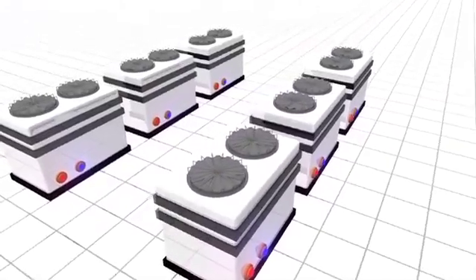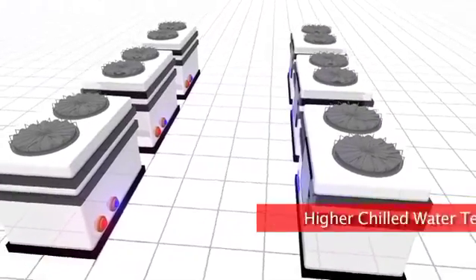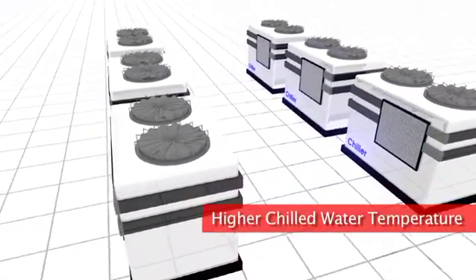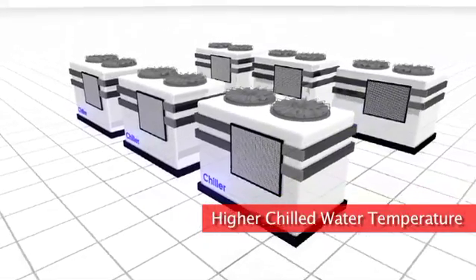With the hot aisle containment we were able to raise our chilled water temperature. This for us meant that we could get between four to six thousand hours a year of free cooling and that directly translates into about a million dollars a year in power savings once the facility is full.